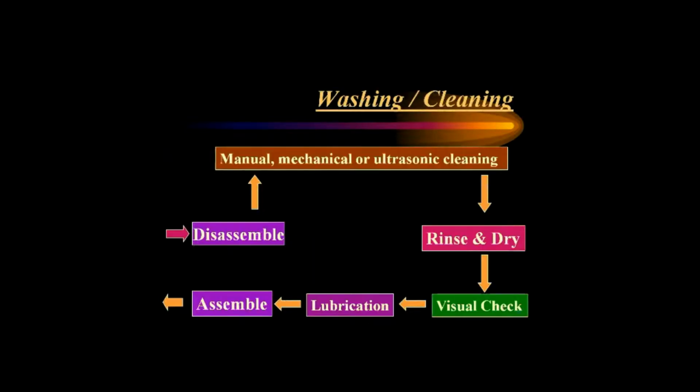Next slide. Coming to washing in particular, as we already know, all the hand instruments are in modular units. We need to disassemble them and take them for manual, mechanical or ultrasonic cleaning.